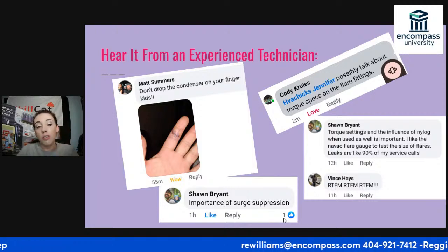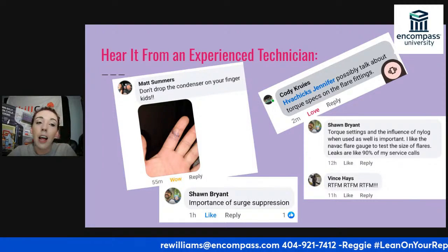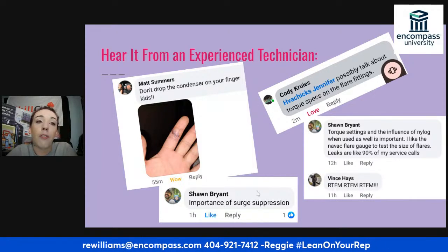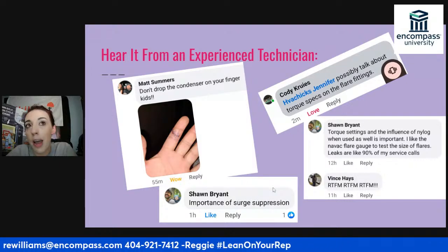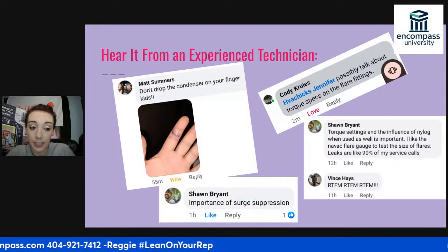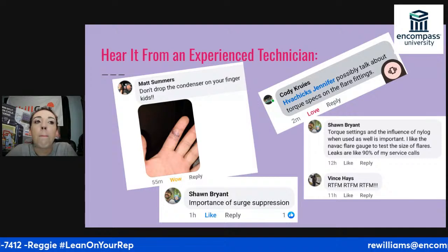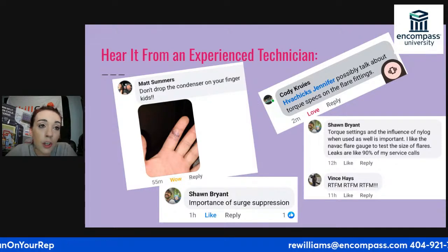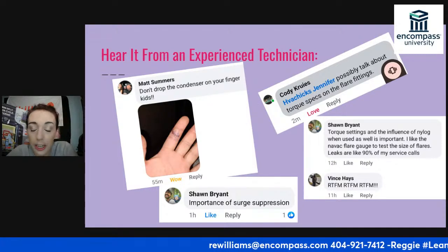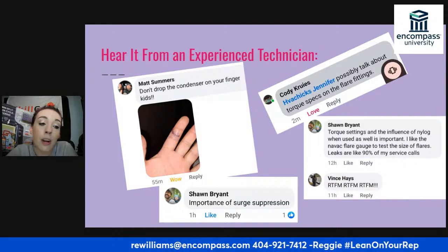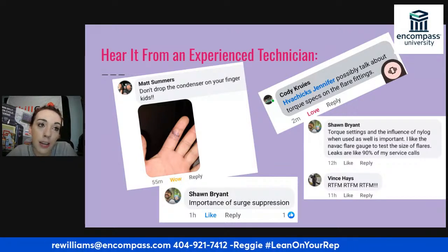When we were talking about melted wires, surge is a factor. Say you have a lightning strike or the power shuts off quickly and acutely, you'll have surges. If you don't have surge suppression or protection, you end up with cooked run start components. That's what I was getting at.